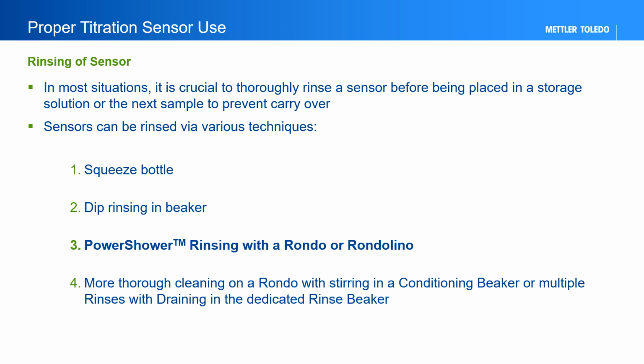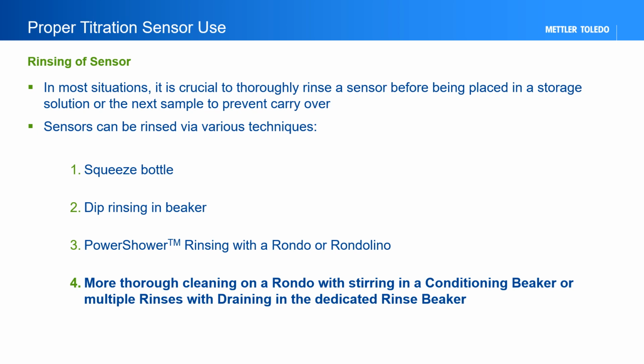When using an automated sample changer, the power shower can be used for effective rinsing of all titration components, including the sensor. If more thorough rinsing than just one rinse coming out of the sample on a sample changer is necessary, a dedicated rinse beaker can be used.